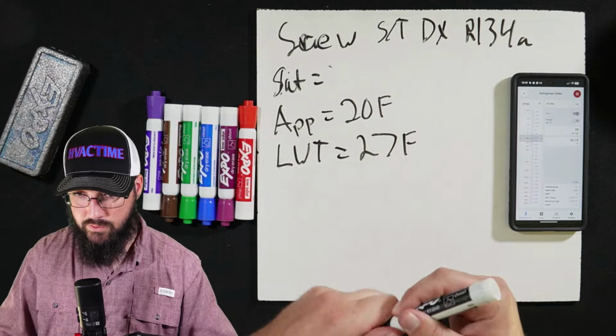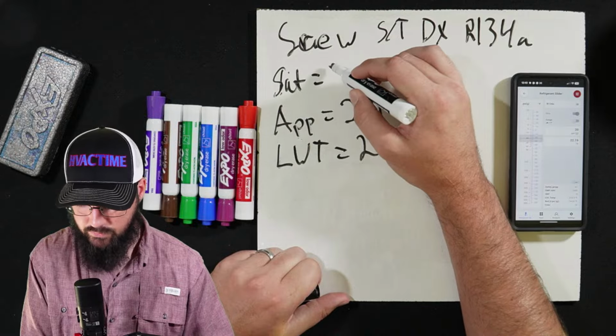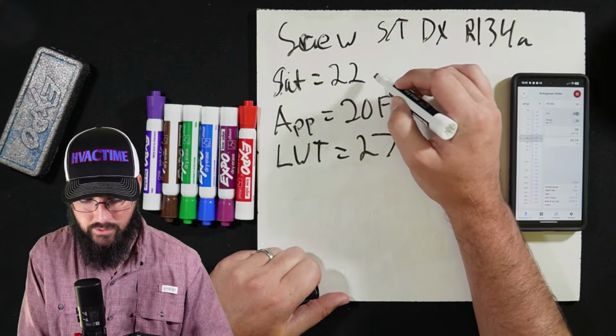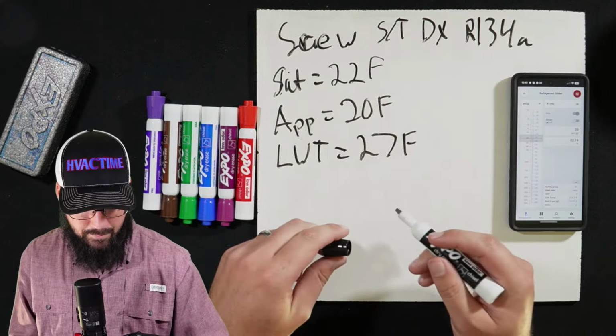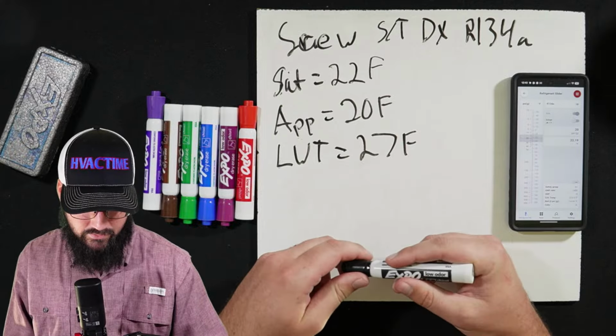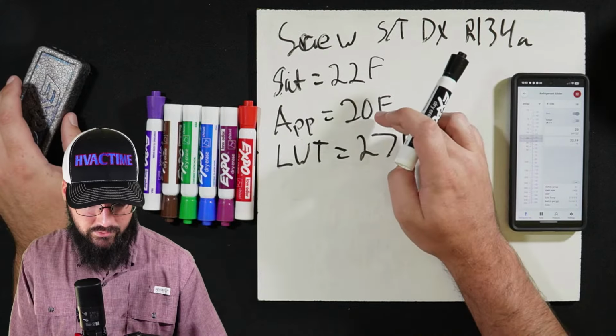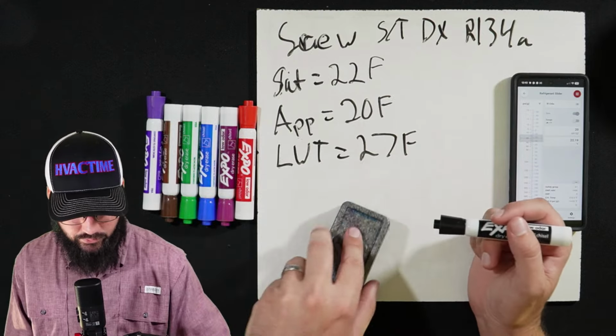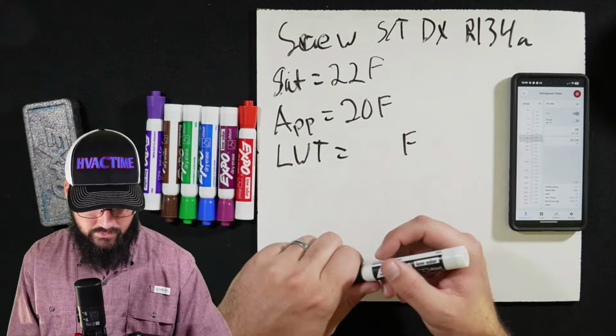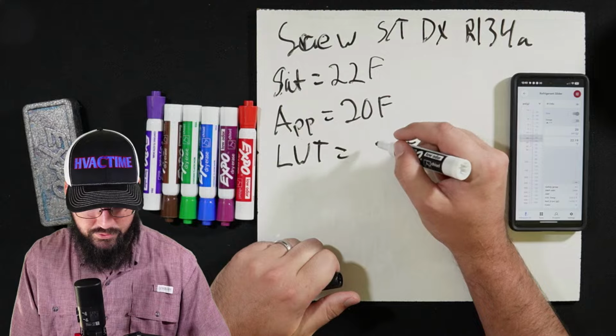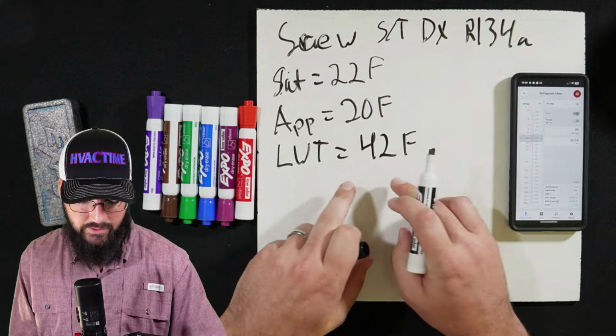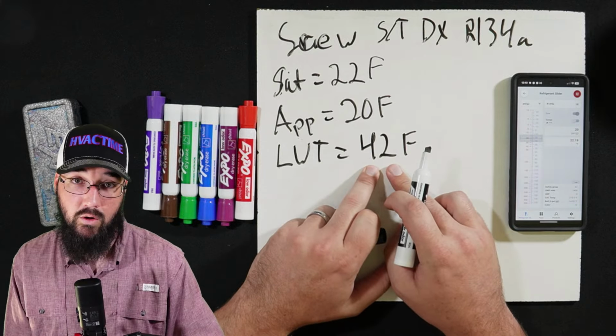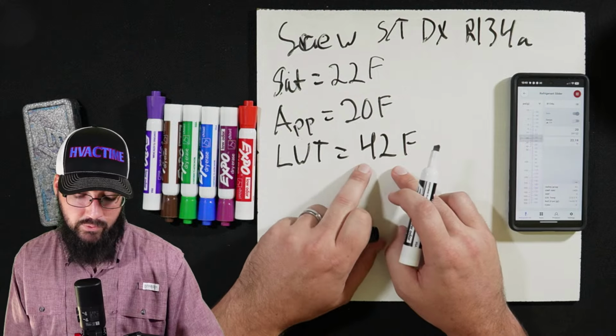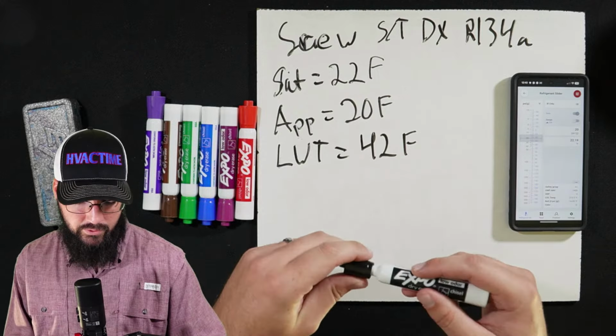So the normal is getting down to 20 psig, which gives us a 22 degree saturation. So if we update that 20, that puts us at what, 42? If our approach is 20, that takes me back to, that gives you a leaving water of 42. This would tell me a low load.